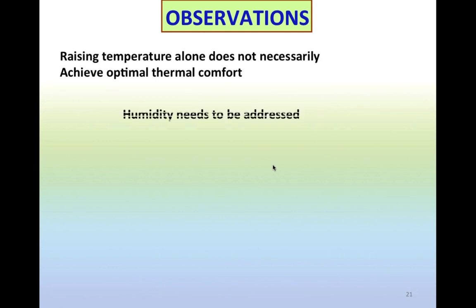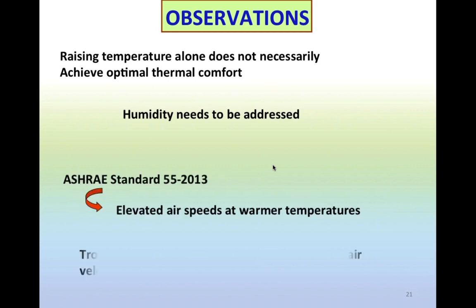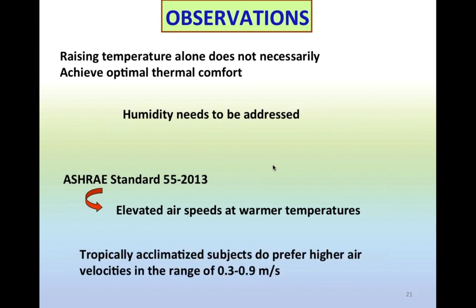And in our observations here, we go on to say that temperature alone being raised may not achieve the optimal thermal comfort, especially with a system that was designed to be operated under totally different conditions. It was supposed to be operating under the lower temperature conditions. Humidity needs to be addressed, and the air movement part needs to be addressed. And this is where I would like to bring about what is now a recommended practice, and we certainly appreciate what can be done here. Elevated airspeeds at warmer temperatures certainly is a good way to go. When you increase the temperature with increased airspeeds, it certainly provides a better level of comfort.